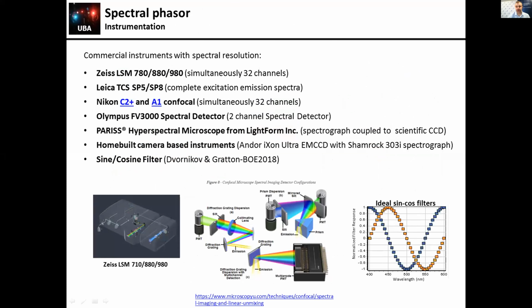They use different kinds of optics to produce basically the opening of the spectra, diffraction gratings, or also prisms, and different configurations where you can project all the light on the array, or you can take the spectra one by one, moving the prism and selecting with your PMT one of the bands that are passing through.